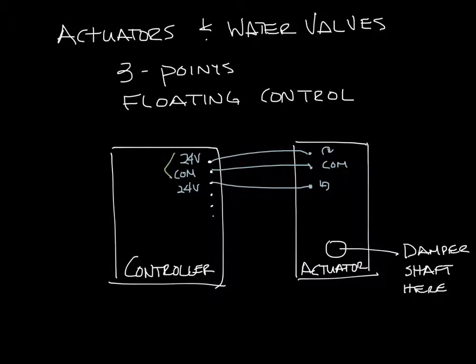Now if you energize these two, the 24-volt on the clockwise and the common, it would turn clockwise or open. And if you energize these two, the common and the other 24-volt that's connected to the counterclockwise, it would rotate counterclockwise and close the damper.